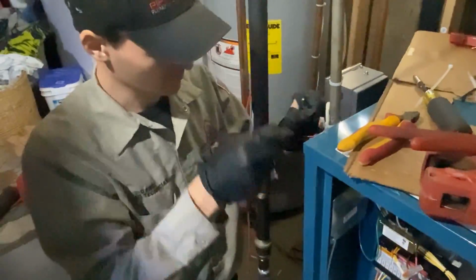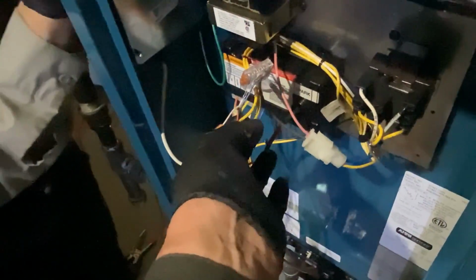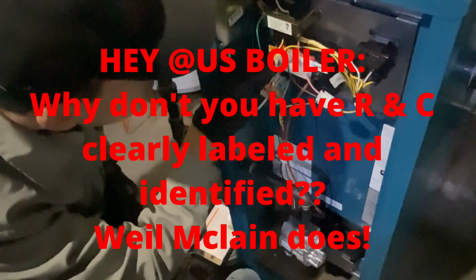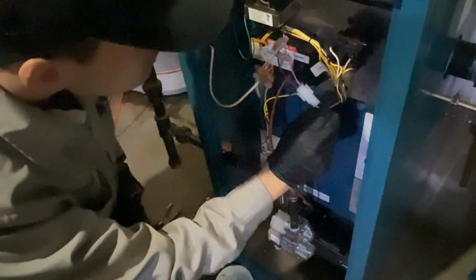So now, once that's reconnected, because it's connected there, basically what that is, you have 2 yellow wires here. They're not identified which one's R and which one is W, but one of these yellow wires is carrying 24 volts, and that's our R. And again, US Boiler, Burnham, if you're listening, another deficiency that you should change on, and that is having clearly marked terminals R, W, and common.